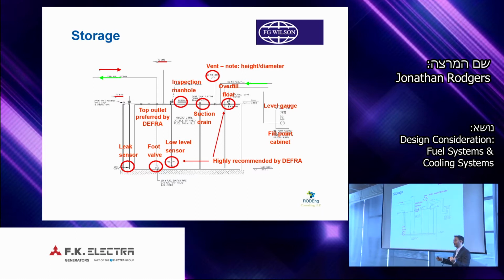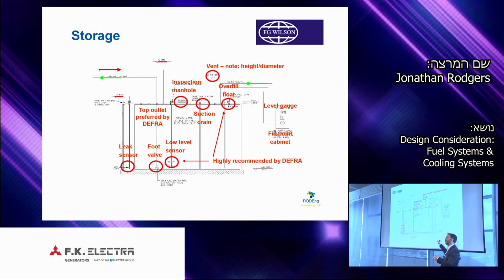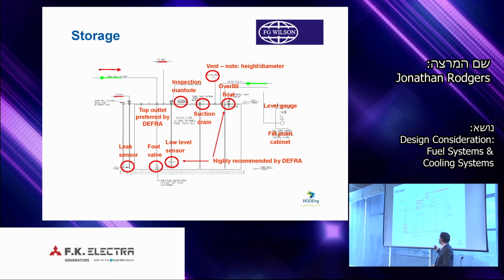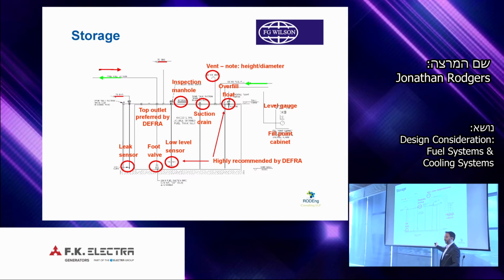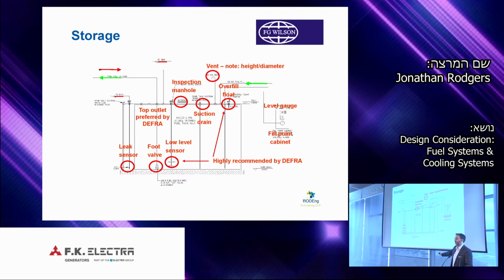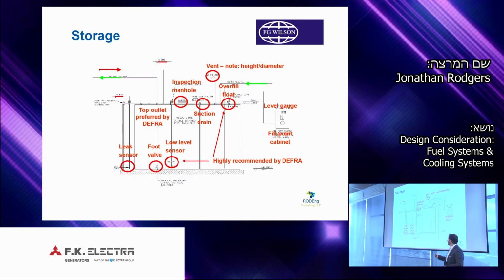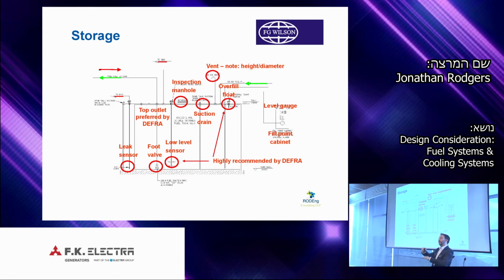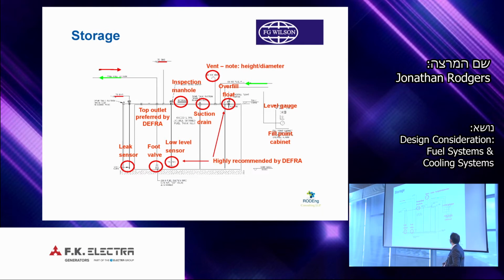And the area of that outlet will relate to the pressure capability of the tank. That relates to the welding of the sides of the tank and the type of tank and type of construction. There may be remote fill points. Quite often we may have a fuel tank in a basement, and we could have a fill point 120 meters away at a different level. And we look at the sizing of the fill point and alarming. We may have foot valves, and this is to protect from debris being sucked into the line. They should fill back to level gauges.